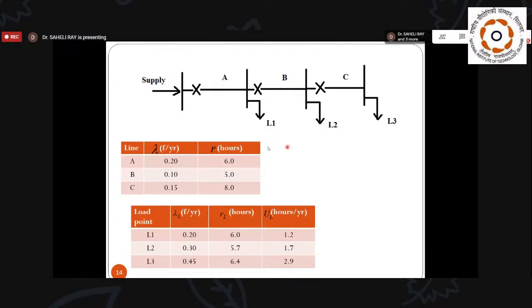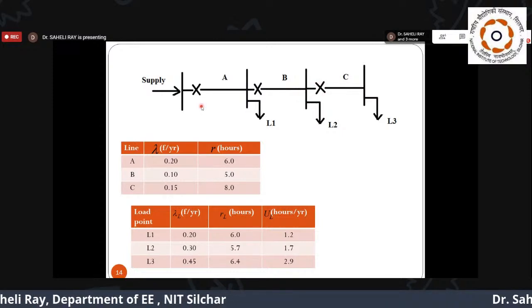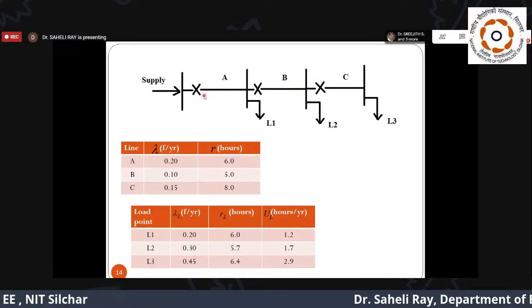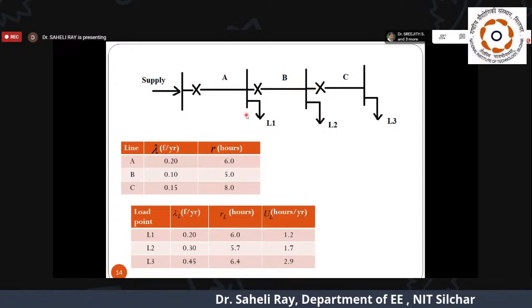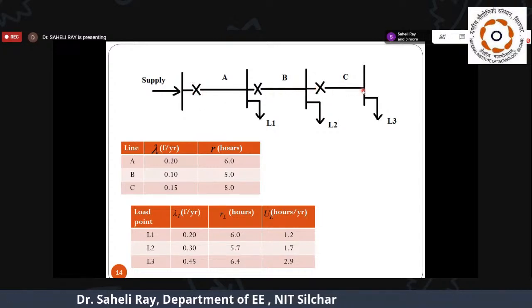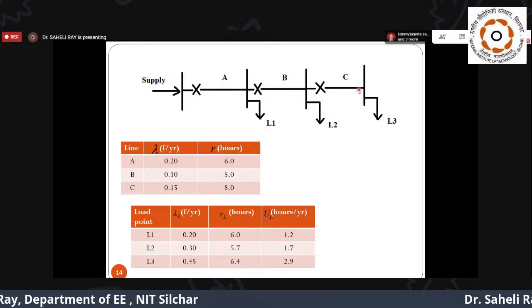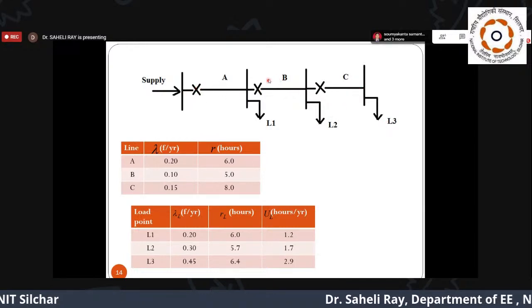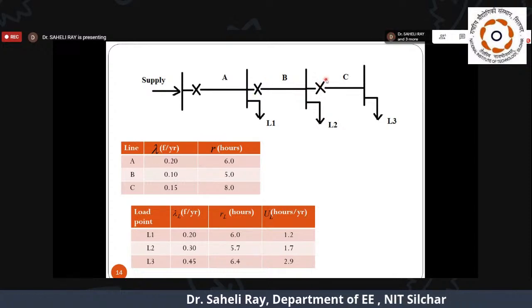This is a radial system. For basic analysis, we consider a system with 3 segments and 3 load points, L1, L2, L3. Suppose at the beginning of each segment there is a circuit breaker, shown by the cross signs. In a practical radial network there may be a circuit breaker only at the beginning, but for calculation purposes we consider this a 3-segment system with circuit breakers at the start of each segment.